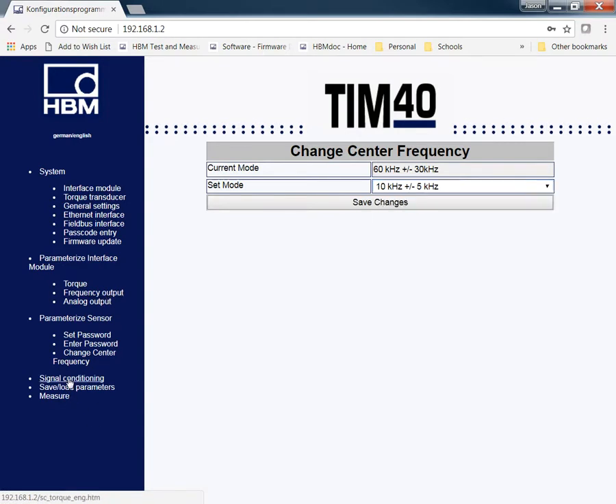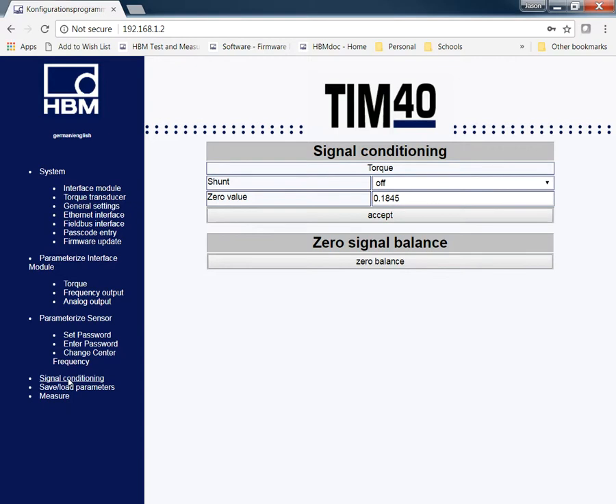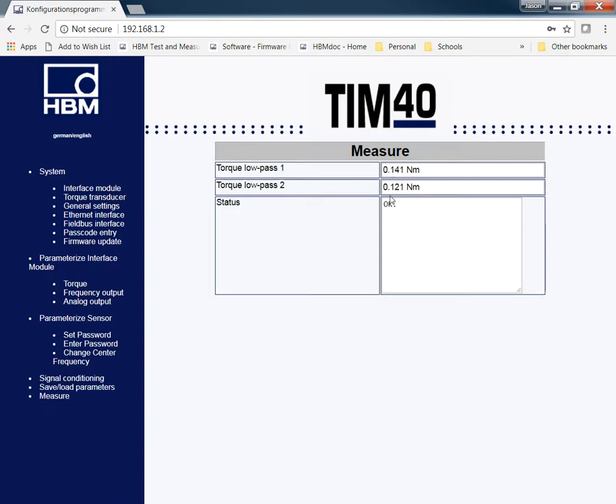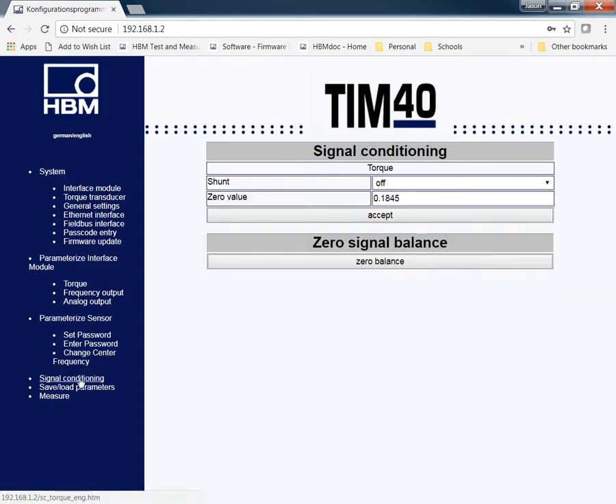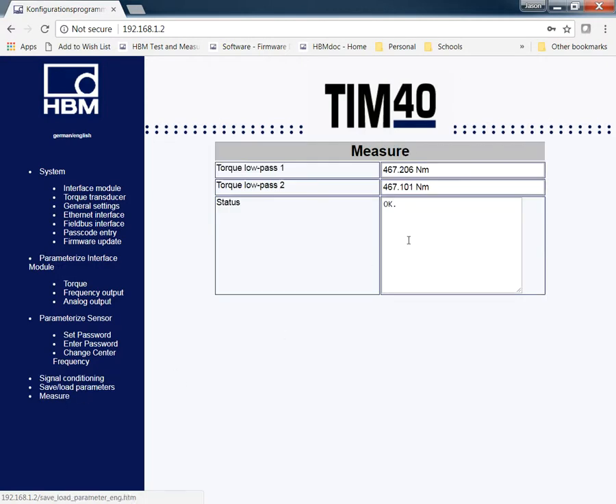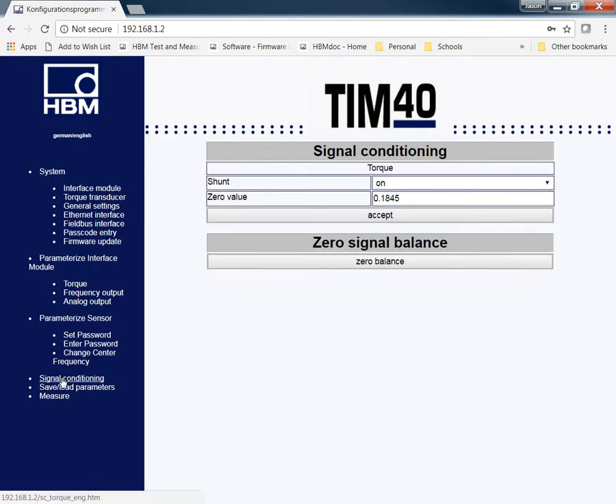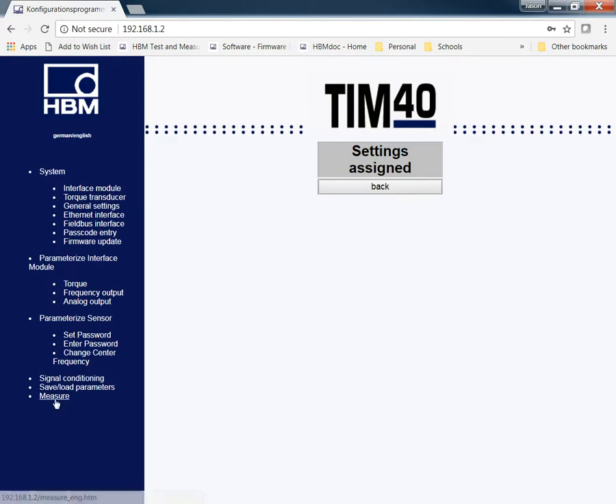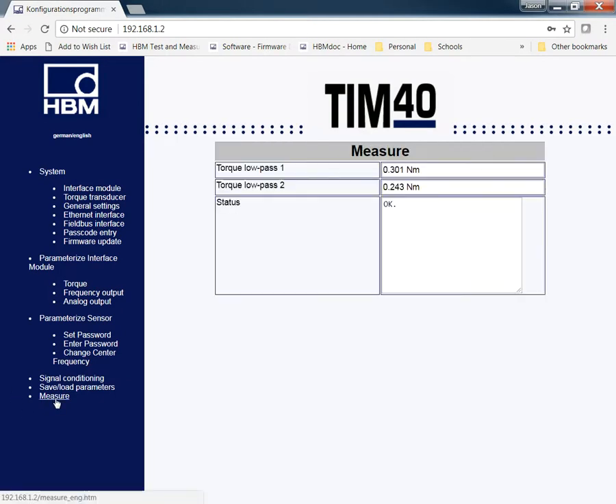In your signal conditioning tab, this is where you can go through and put in your shunt value. I'm going to turn this shunt on and I'm going to click the measurement tab on the bottom left here to give me some values. There's my zero value that it's reading. Go through and turn on my shunt. You have to hit on and then accept. This is going to be half of your load, and this is what's detailed on your calibration sheets. I'm going to go back and shut this one off. Anytime you make a change, you have to hit the accept button underneath. If not, it's not going to change. Just be aware of that as you go through. There's my zero values again.